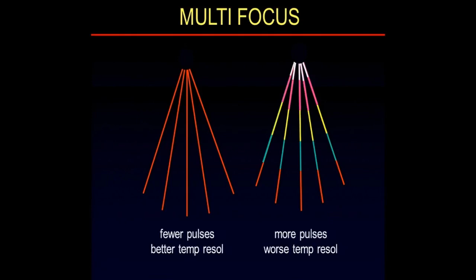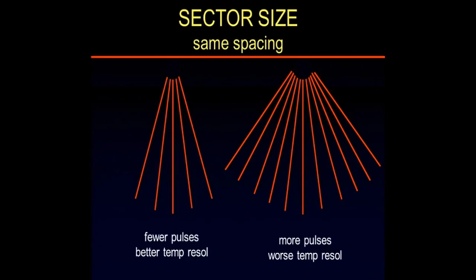Sector size. We can have a wide sector or a narrow sector. That's a narrow sector. That's a wide sector. Well, the narrow sector uses fewer pulses, takes less time, has a higher frame rate. Improved temporal resolution. Now you notice here that the spacing between the lines is unchanged. That's a subtlety. We don't really see the line spacing. But there actually is a control that does that.